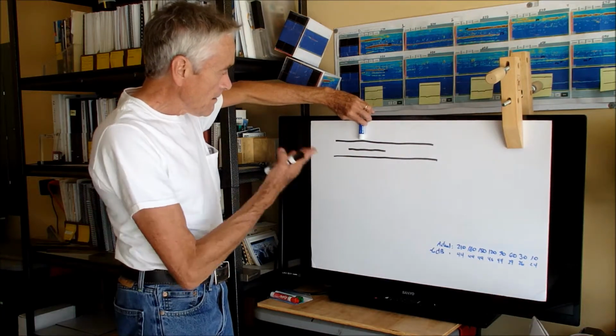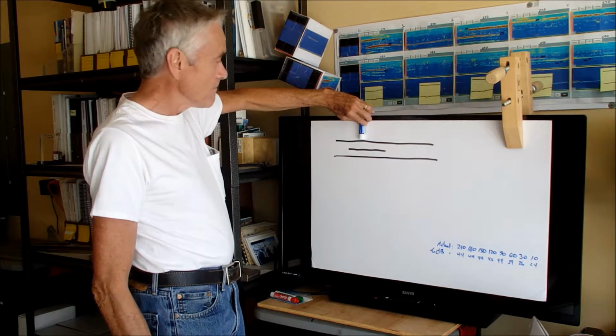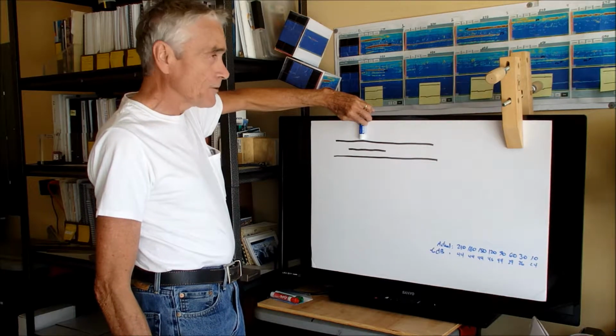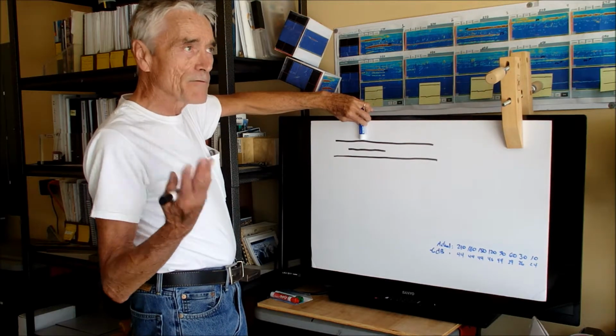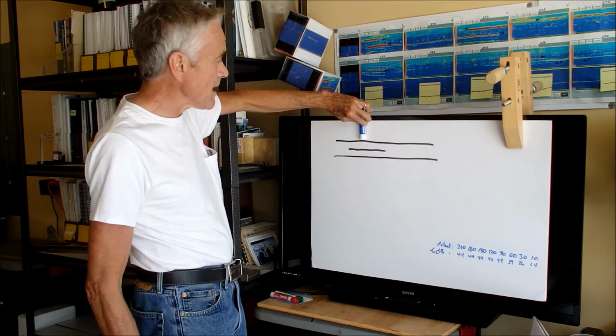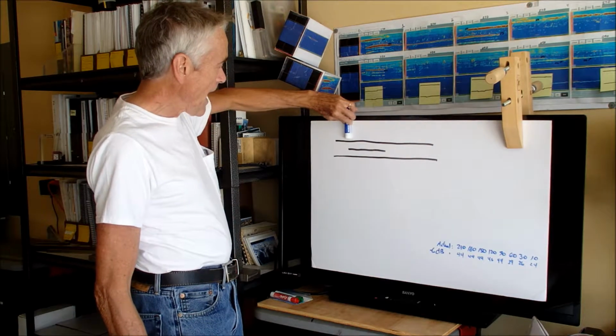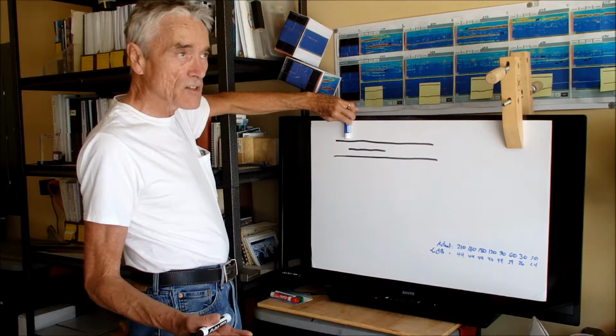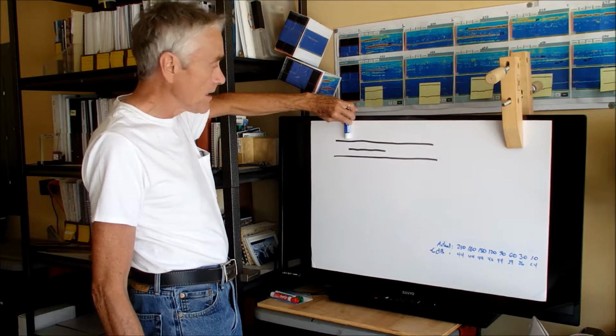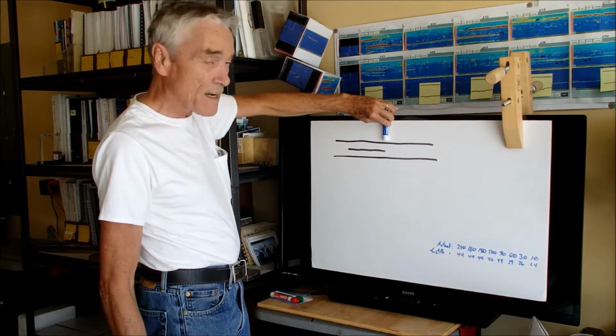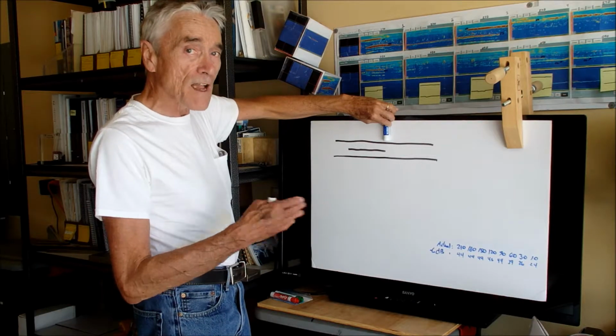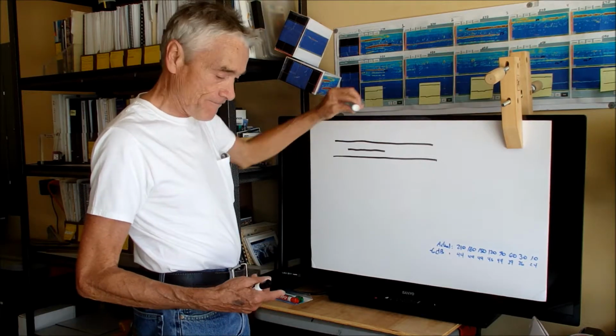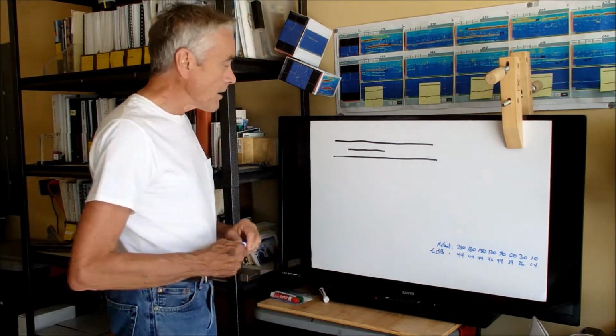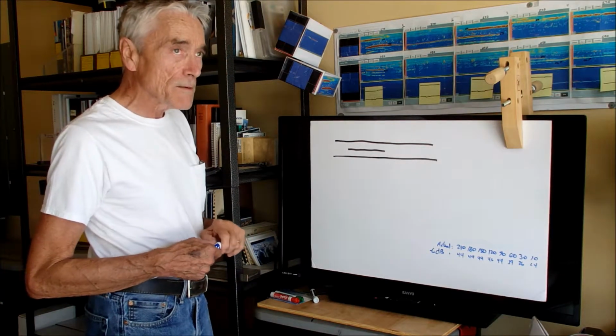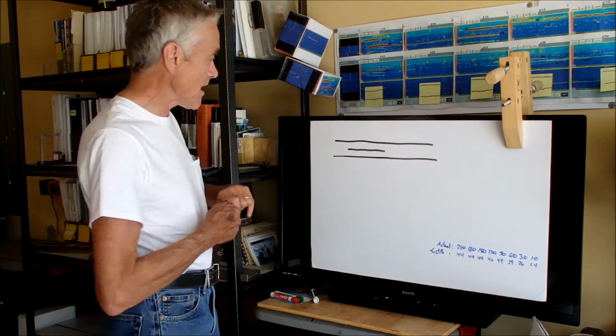Then if you have a certain loudness here and some amplitude and you brought it to, like we did before, let's say you brought it to 80% screen height, when you were halfway over the edge you would be 6 dB less, you'd be at 40%. So you could use this technique to bound the outside edges of a large lamination. Another time when you could do 6 dB drop sizing is for flaw length sizing.